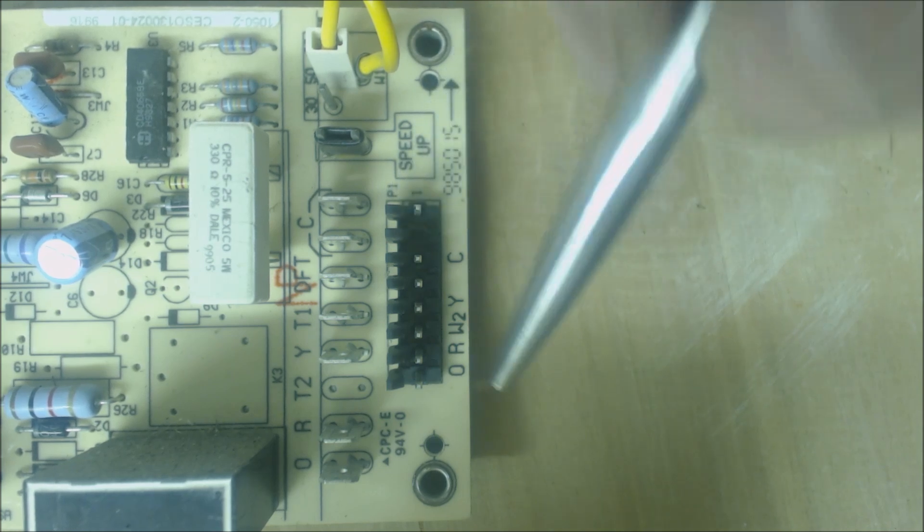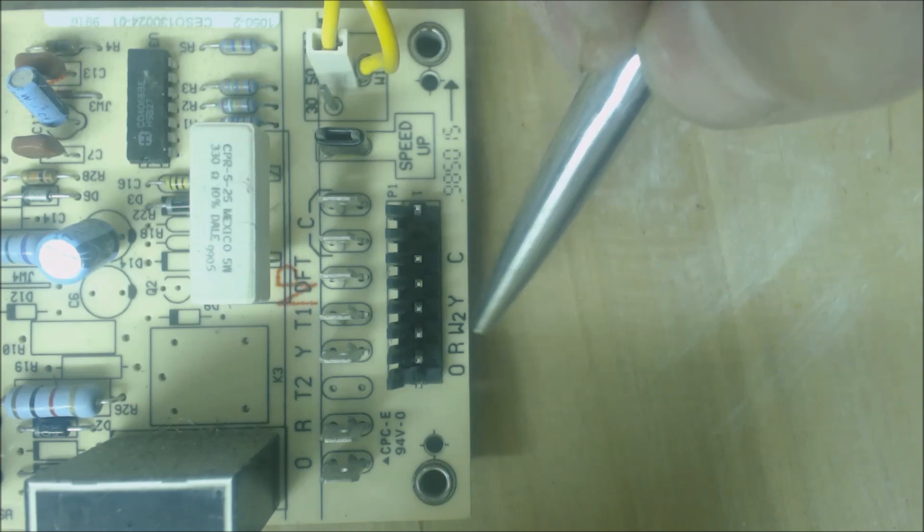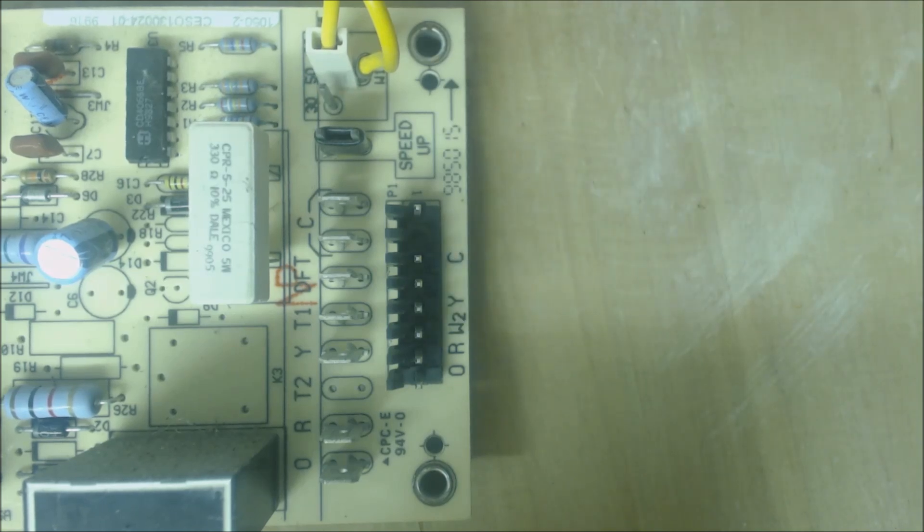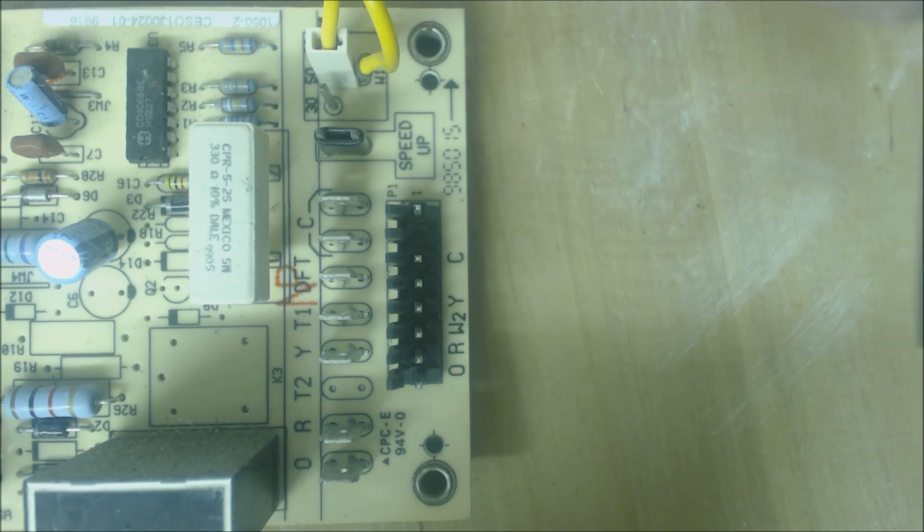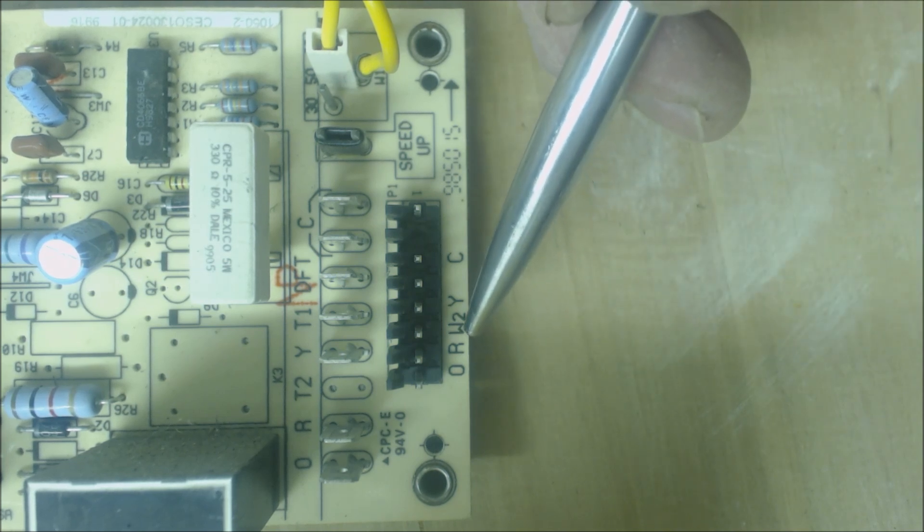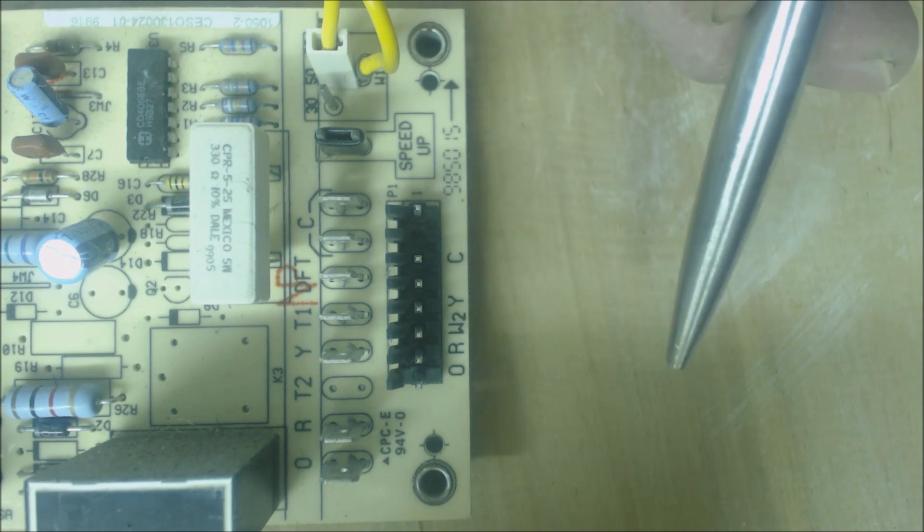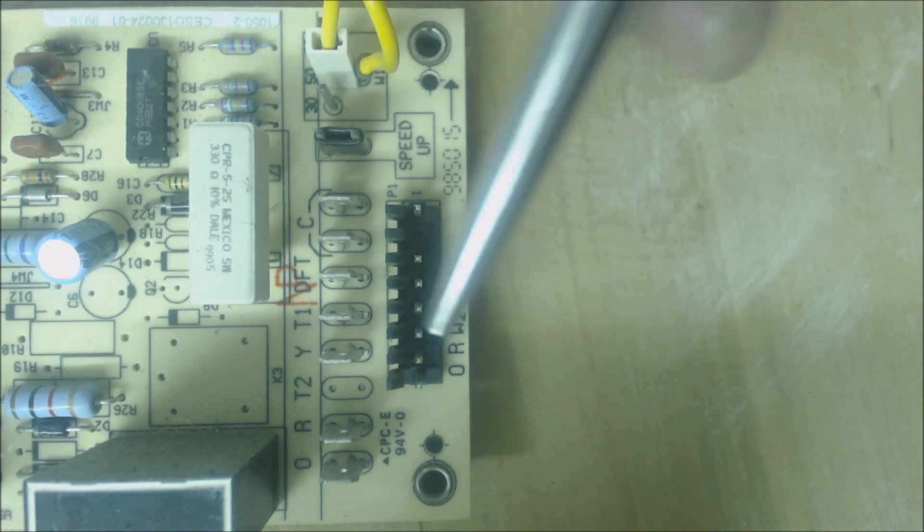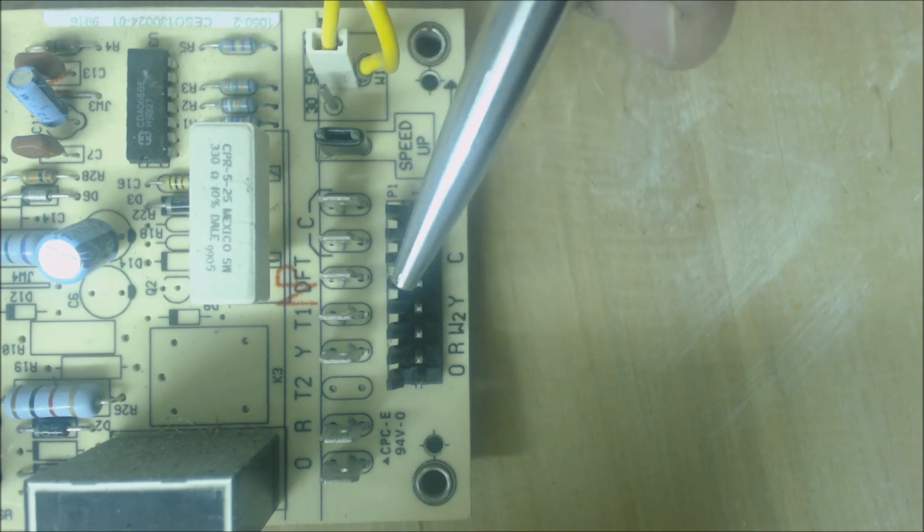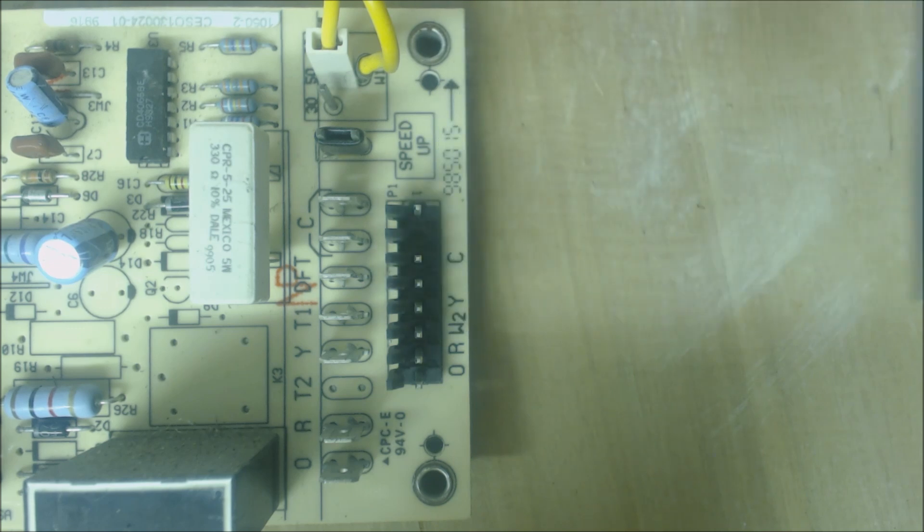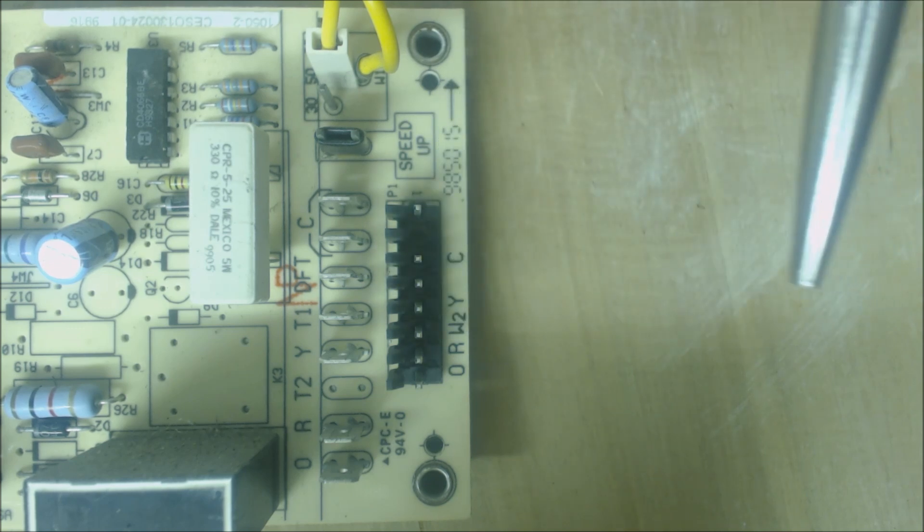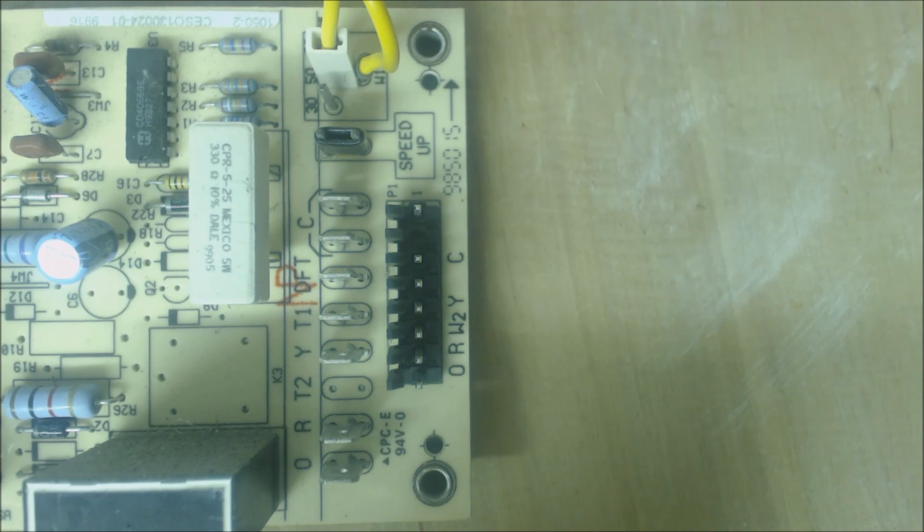W2 is going to send the signal to the indoor air handler telling it to turn on the electric resistance. The electric resistance is also going to dump heat into the refrigerant. The refrigerant is going to absorb that, bring it back to the outdoor unit, and it's going to help the outdoor fins reach a higher pressure, which means a higher temperature.